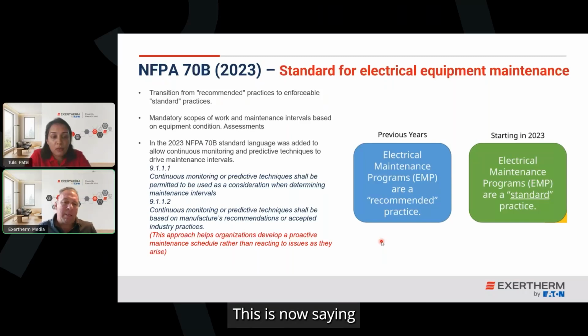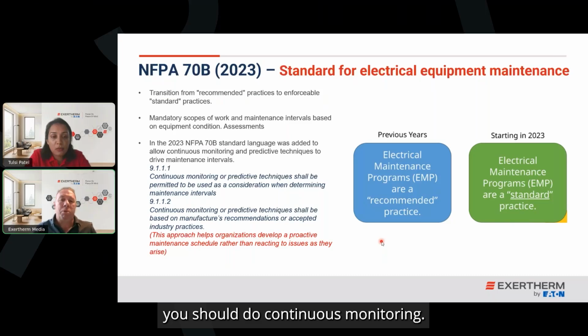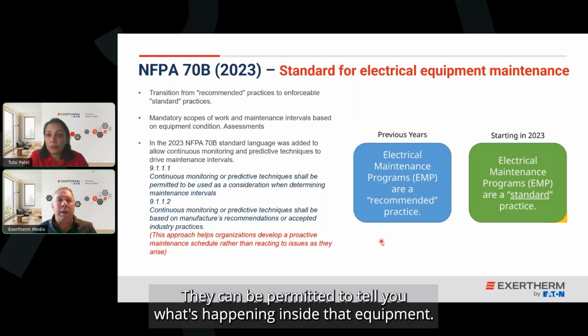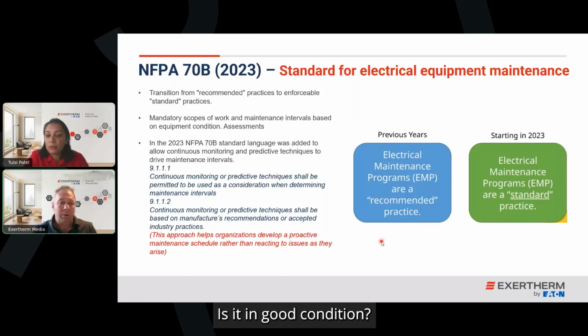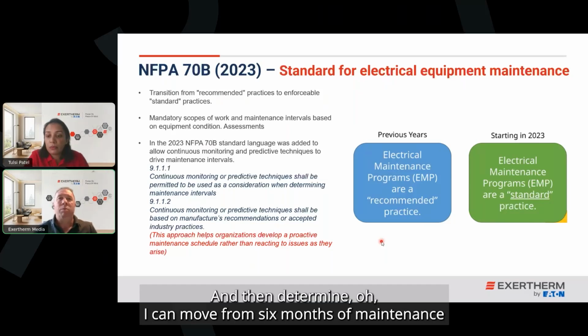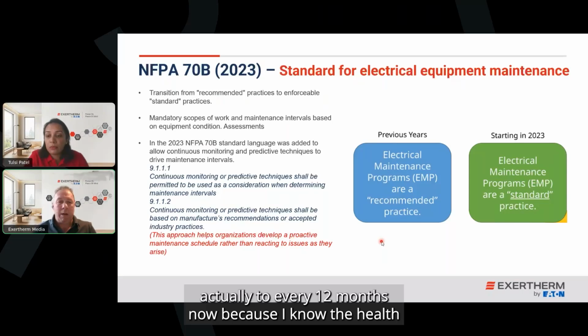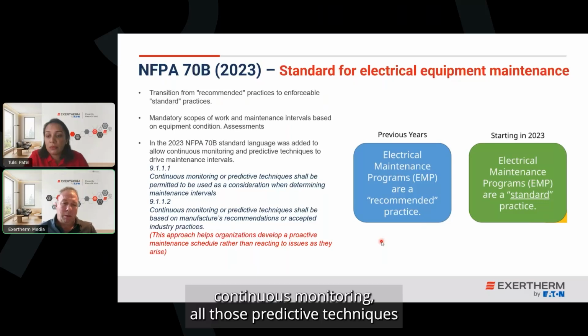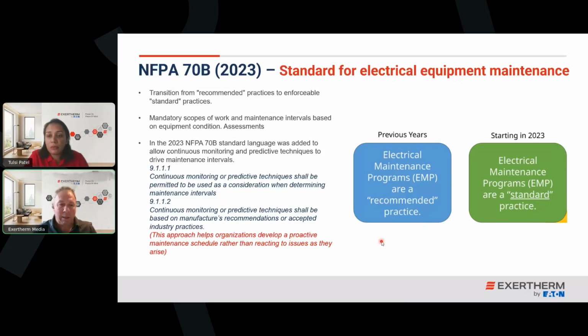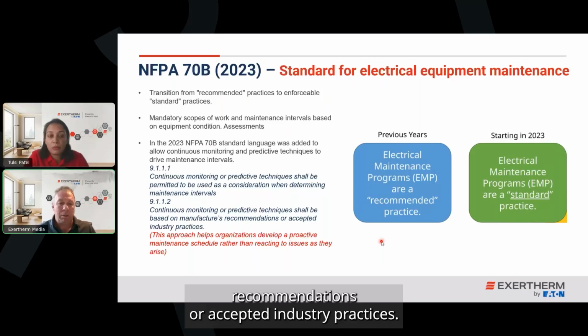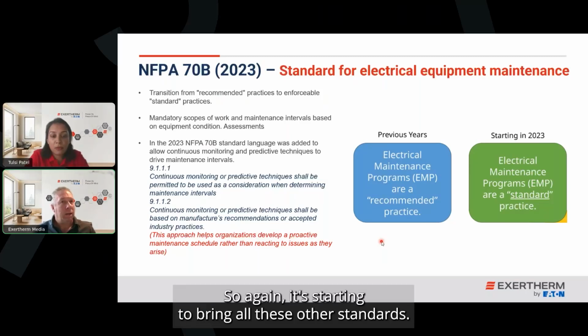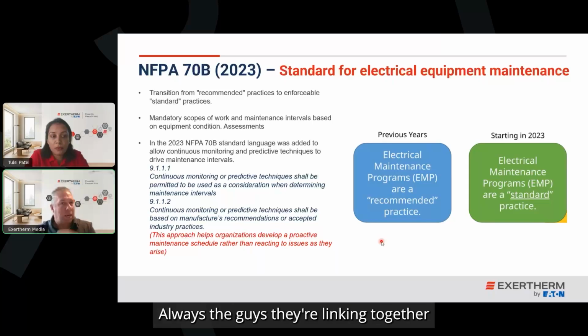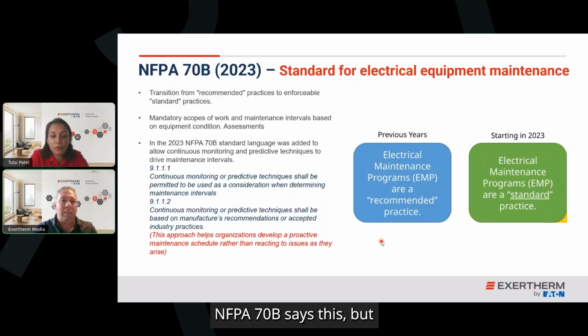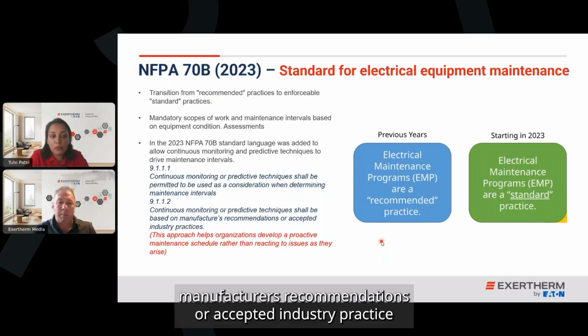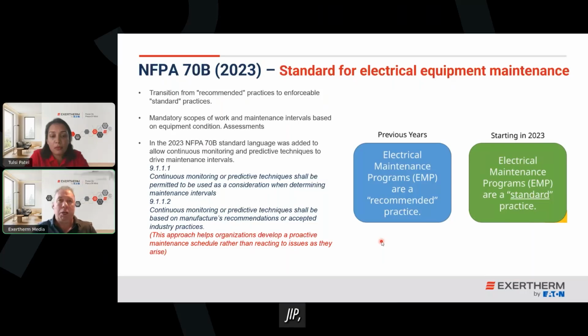Happy days. This is now saying you should use continuous monitoring. They can be permitted to tell you what's happening inside that equipment. Is it actually healthy? Is it in good condition? And then determine, oh, I can move from 6 monthly maintenance actually to every 12 months now because I know the health. But also continuous monitoring, all those predictive techniques shall be based on manufacturers' recommendations or accepted industry practices. So again, it's starting to bring all these other standards, all these other guides, they're all linking together. NFPA 70B says this, but manufacturers' recommendations or accepted industry practice, IEEE, they're all linked.